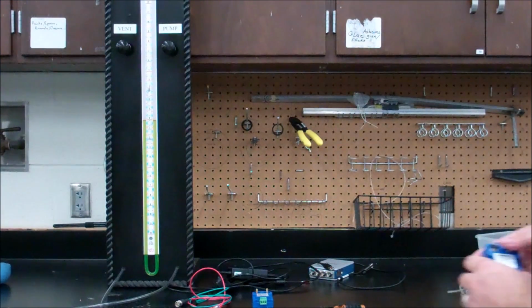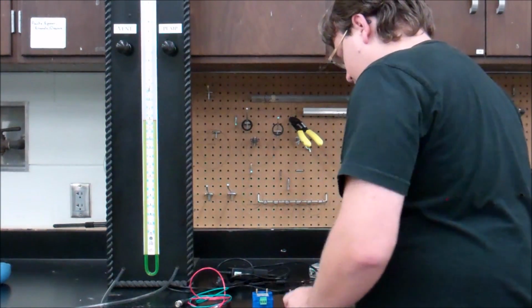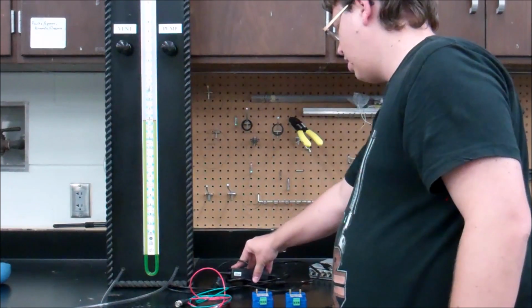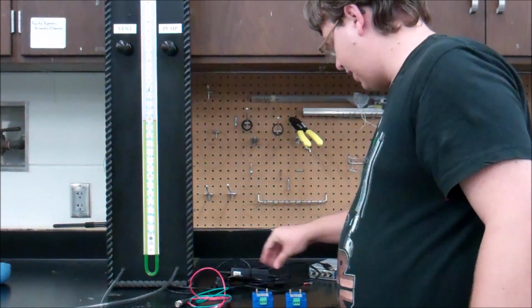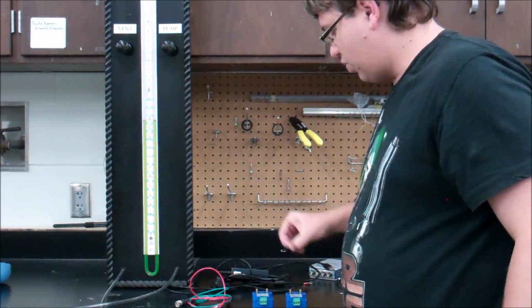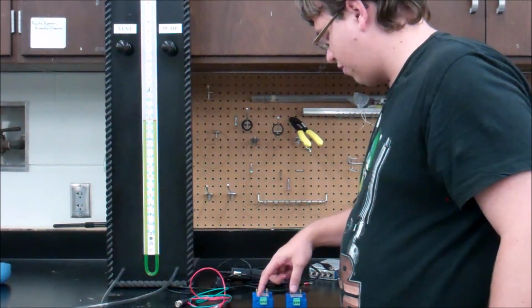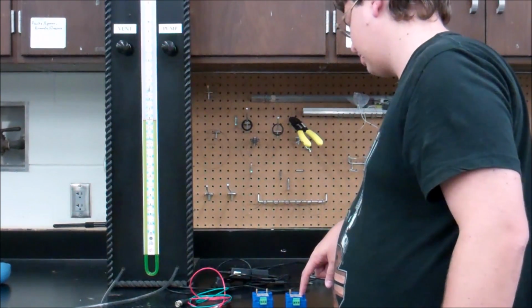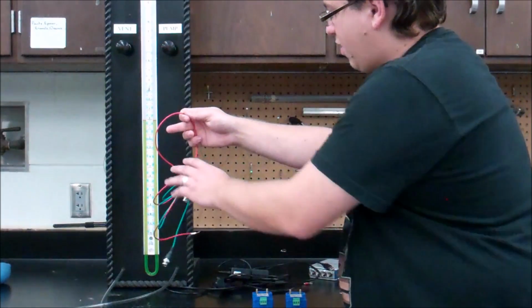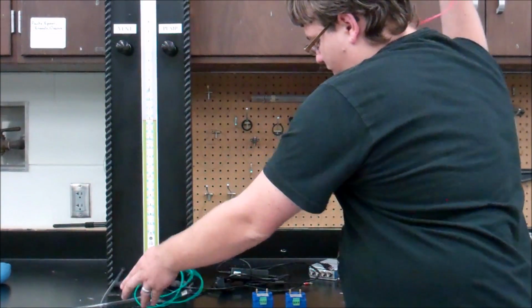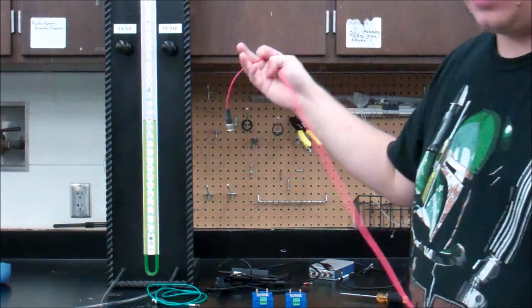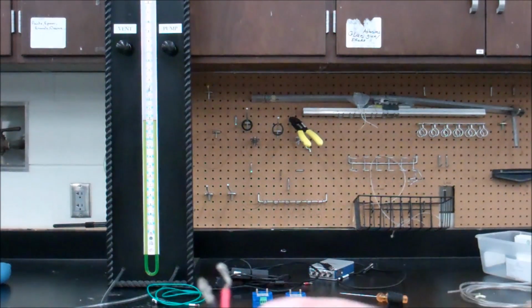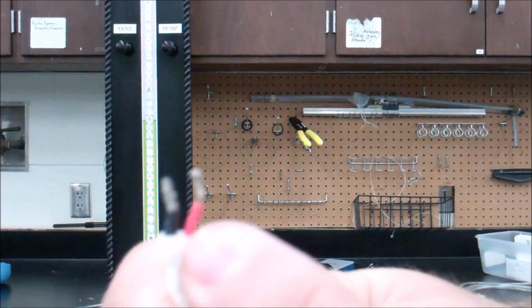So what we're going to do is we're going to connect the V in and COM to the power supply. Then using the 2 wires, we're going to jump the V in and the COM from one pressure transducer to the other pressure transducer. And then we're going to take each BNC cable and connect the red insulation one to the V out and the black insulation one to COM.